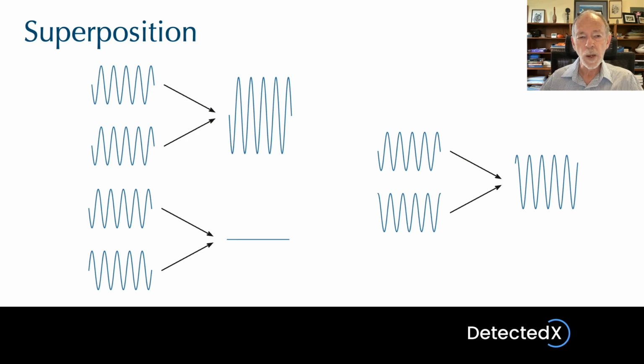Down below that, we have the opposite situation, where the transmitted energy from two different points on the face of the transducer arrives 180 degrees out of phase, or in opposite phase, which means that basically these waves are half a cycle apart in their timing. So when one of them is trying to increase the pressure, the other is equally trying to decrease the pressure. And not surprisingly, they cancel one another out, and the net result is 0.